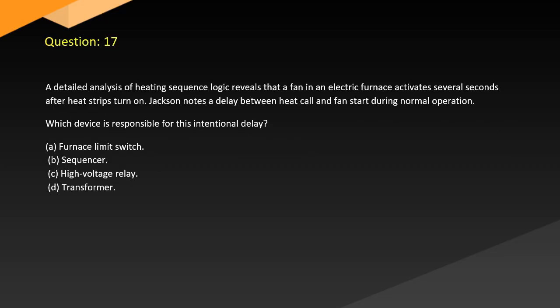Question 17. A detailed analysis of heating sequence logic reveals that a fan in an electric furnace activates several seconds after heat strips turn on. Jackson notes a delay between heat call and fan start during normal operation. Which device is responsible for this intentional delay? A. Furnace limit switch. B. Sequencer. C. High voltage relay. D. Transformer.